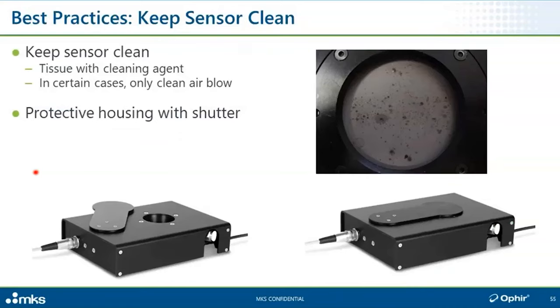Okay, some best practices and tips. Probably the first one that we really have to start with is keep your sensor clean. What you're looking at here is a thermal sensor with a standard broadband absorber. Apparently some kind of organic debris must have splashed onto the sensor and got burned on by the next exposure to a high power beam. Had they not waited until the next exposure to a high power beam, it would have probably been very easy to clean that off. Tissue with a suitable cleaning agent. On our website, we have some recommendations of how to clean the different sensor types. Most of them, a soft optical type tissue with ethanol or methanol, in most cases is all you need to do.